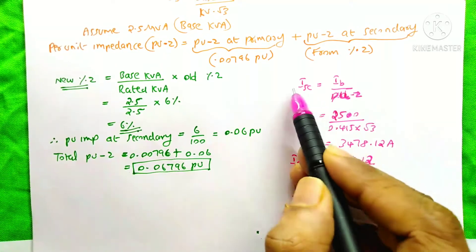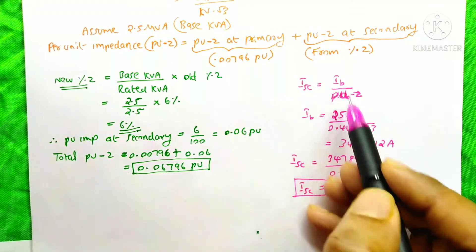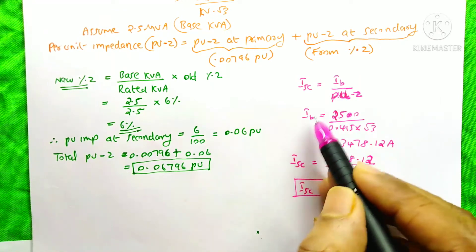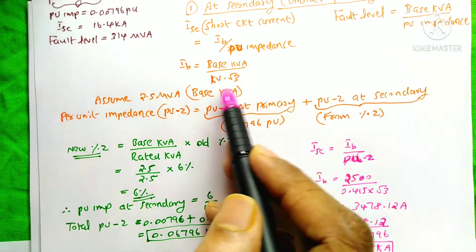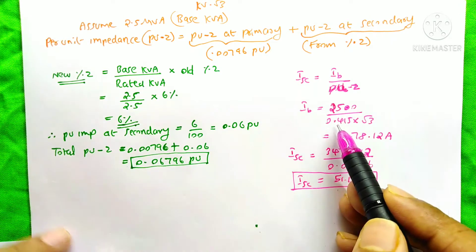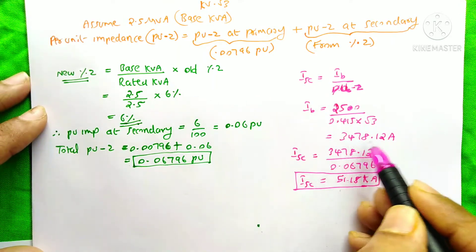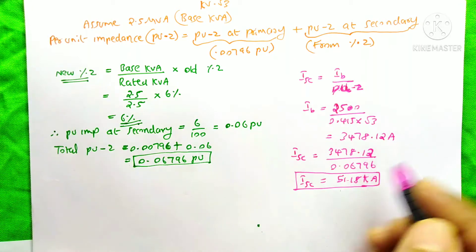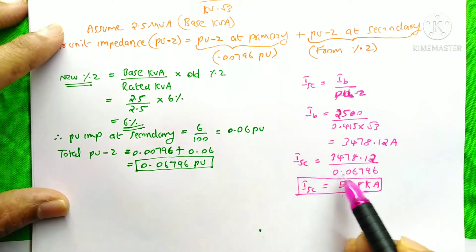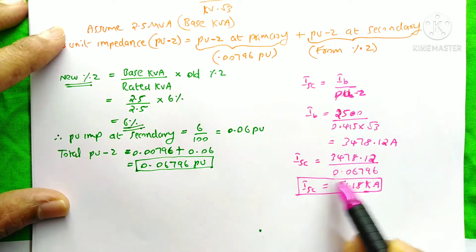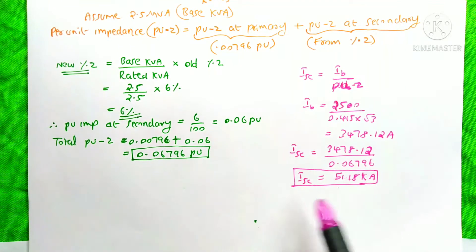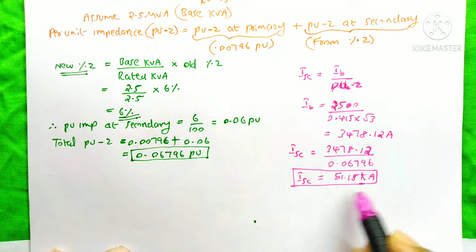For the short circuit current, ISC equals IB divided by per unit impedance. First, we find the base current IB: base kVA divided by kV into root 3, that is 2500 divided by 0.415 into root 3, which gives 3478.12 Amps. Then the short circuit current ISC equals 3478.12 divided by 0.06796, and the answer is 51.18 kilo Amps.